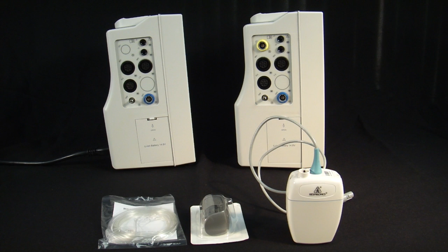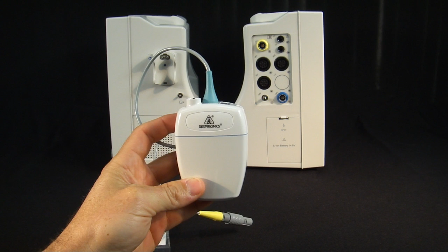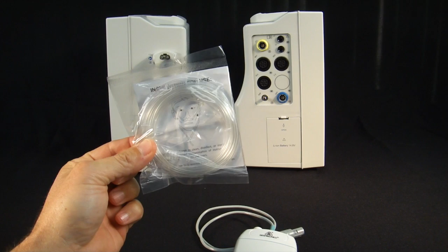The Edan G2 water traps look like a traditional water trap. It goes into the side of the unit, actually would go this way, and then terminates with a Luer lock. The good news is, in the past we've been stuck using Respironics OEM cannula, and I'll show you those options from their support booklet, but at substantially elevated cost. A generic cannula like this might have an end user price of $3 to $5 depending on quantity and configuration. These cannula were $10 to $12 end user prices and up, depending on which cannula you went with or sampling line. So the cost savings is substantial.